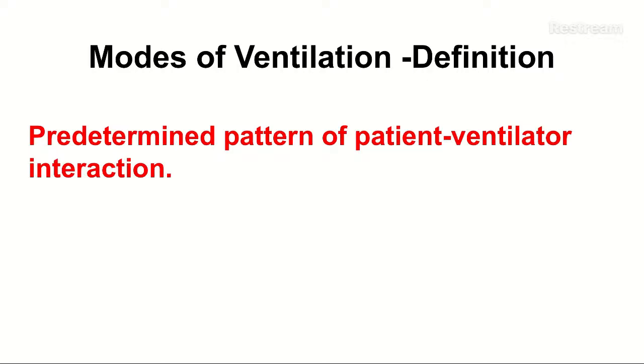So if I say a ventilator is a simple machine, it has some input that we provide through power and pneumatics, oxygen, air. Then we set something on the ventilator, including modes, PEEP, tidal volume or pressure, inspiratory time, and we set some limits. So this is what we set, a predetermined thing, and then it delivers in a certain fashion.